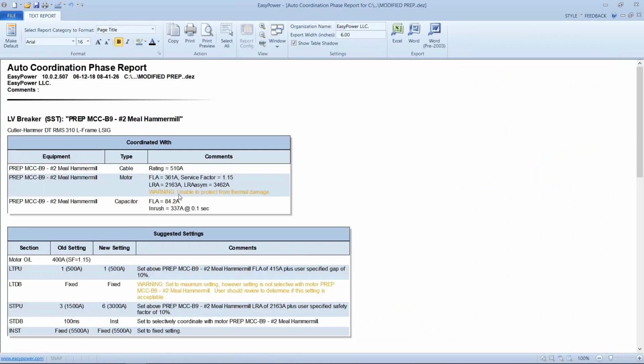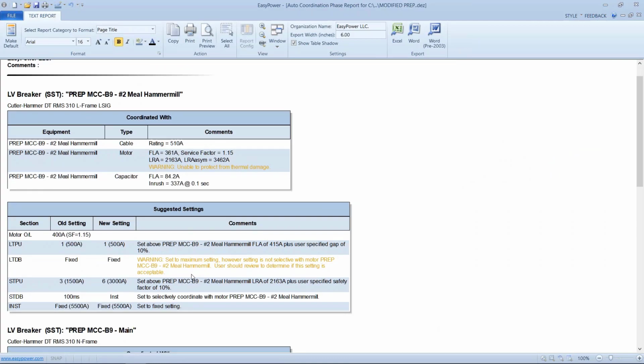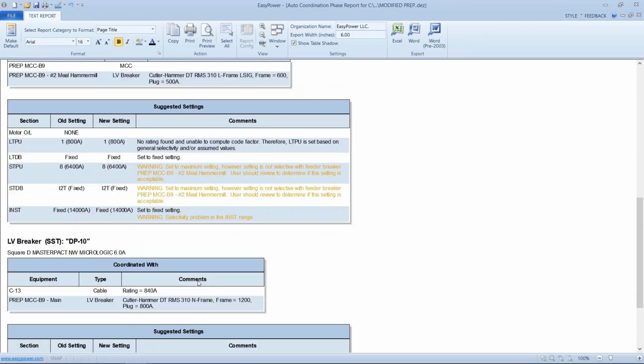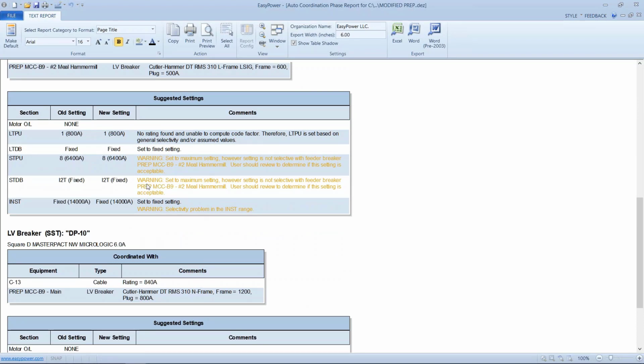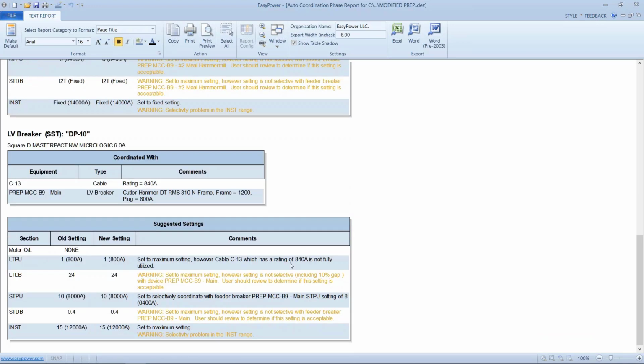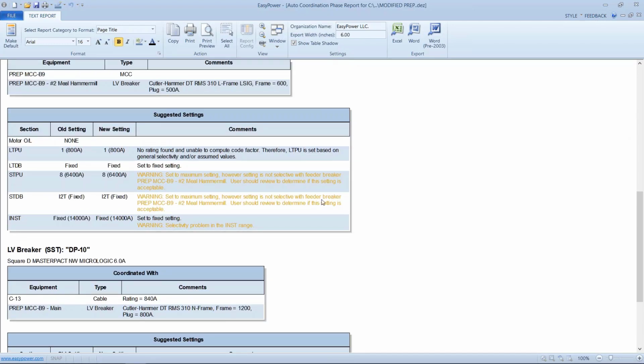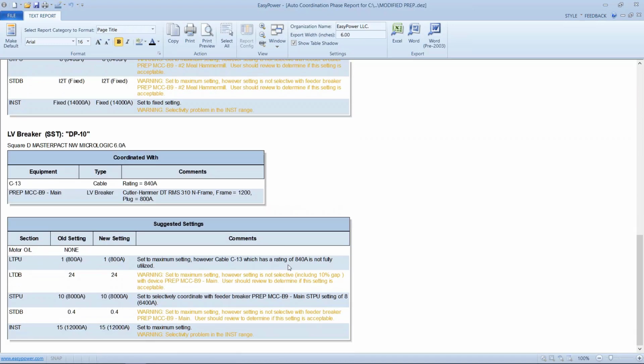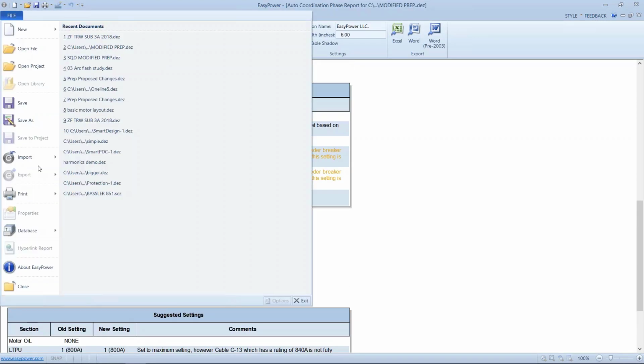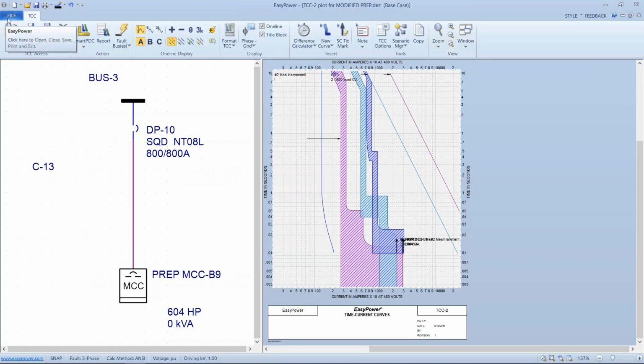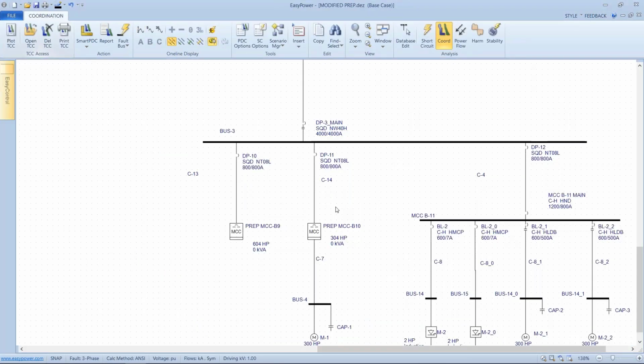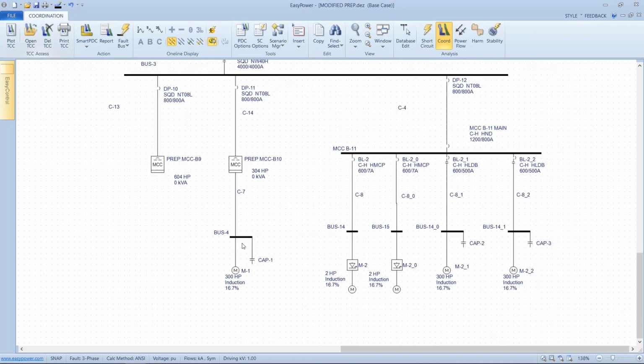More valuable than just a pretty curve is looking at the report, and now this is what shows some areas that really need some consideration by the engineer doing the study. What this tells us is that there are some settings at the maximum that don't really give us the conventional overlap or gap, in terms of clearance between the two breakers. Okay, so bottom line is, when we're looking at a motor control center, we really cannot tell if we've isolated the load. So the next step is to outboard that load.